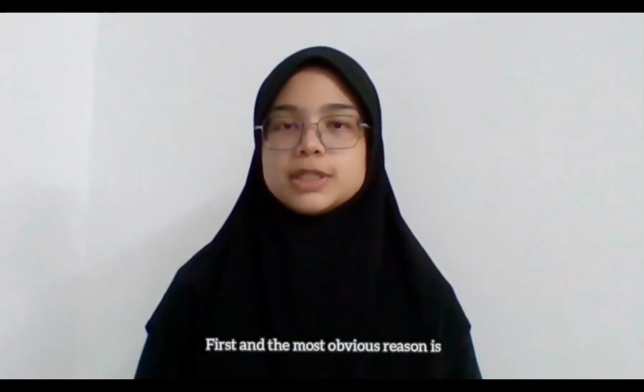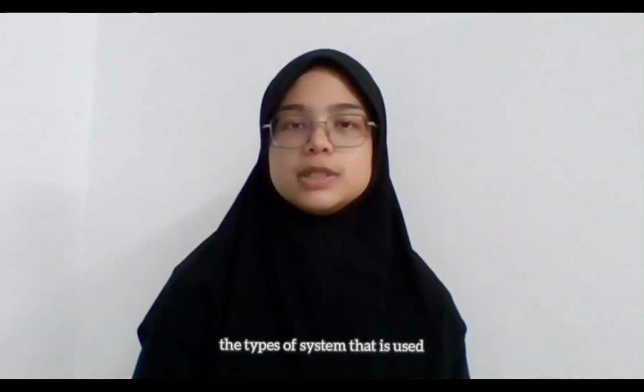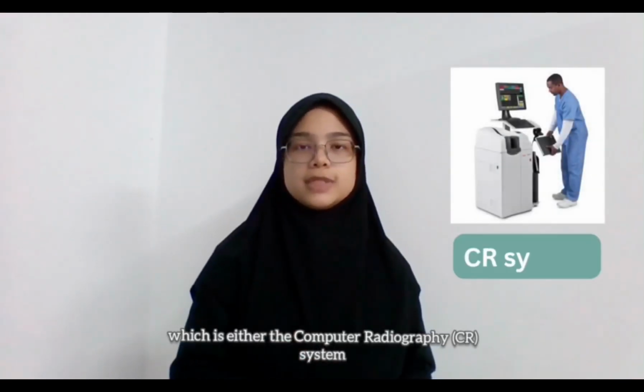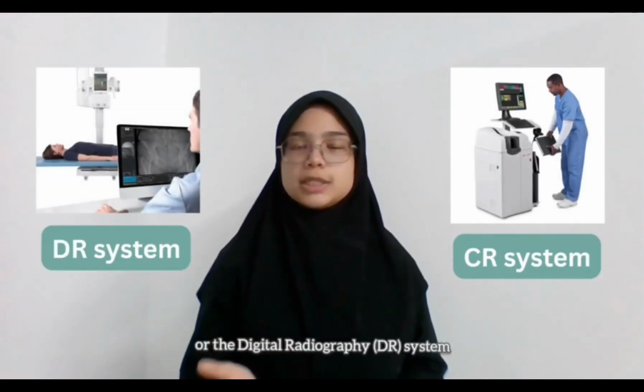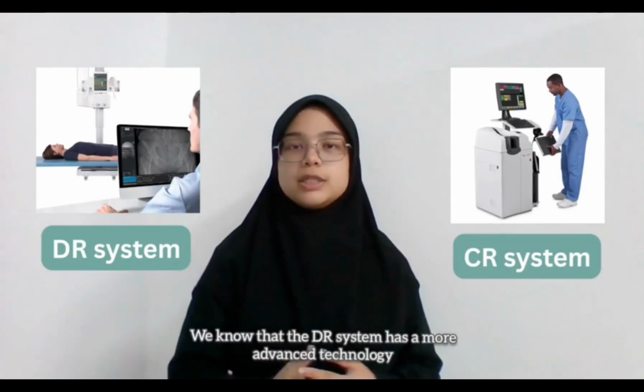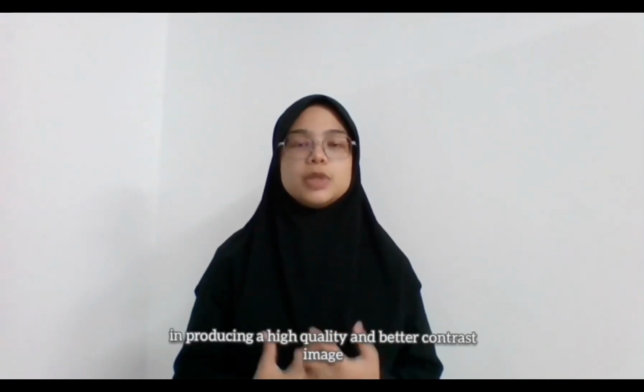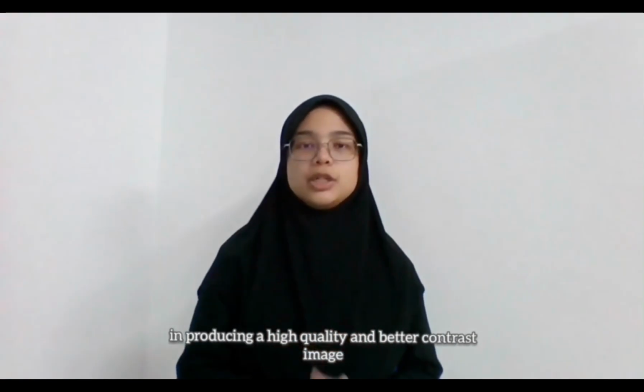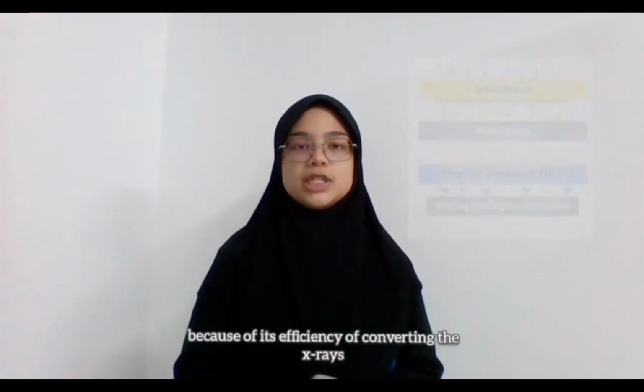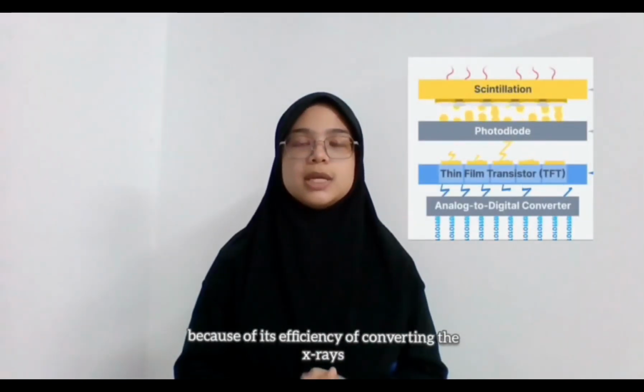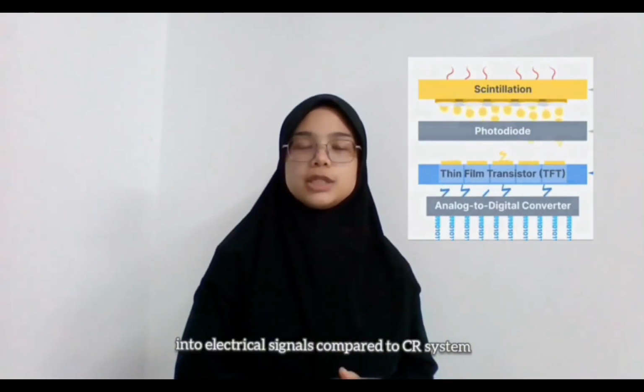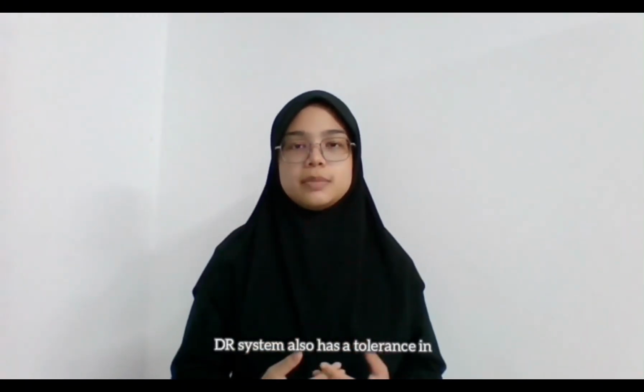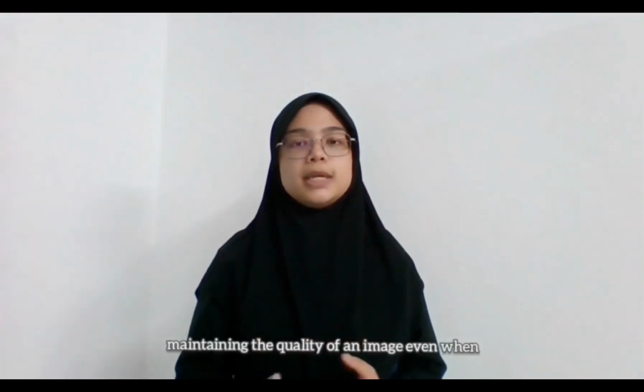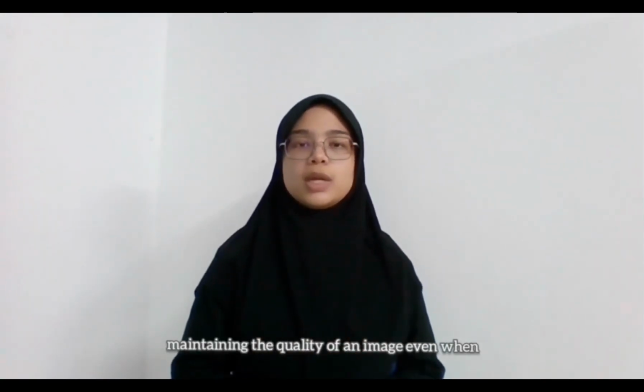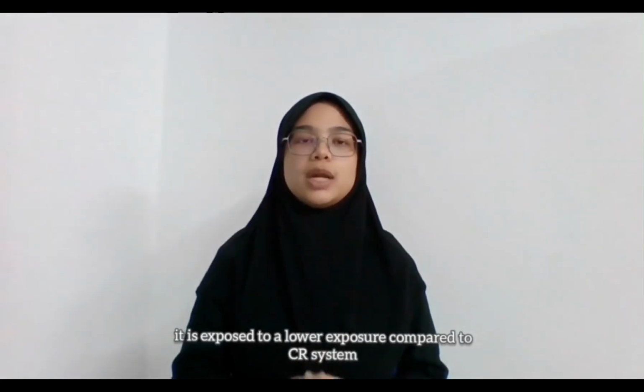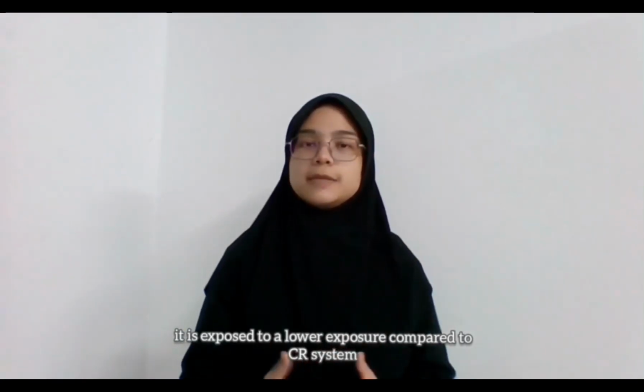First and most obvious reason is the type of system that is used, which is either the computer radiography system or the digital radiography system. We know that the DR system has a more advanced technology in producing a high quality and better contrast image because of its efficiency in converting the X-rays into electrical signals compared to the CR system. The DR system also has a tolerance in maintaining the quality of an image even when it is exposed to a lower exposure compared to the CR system.